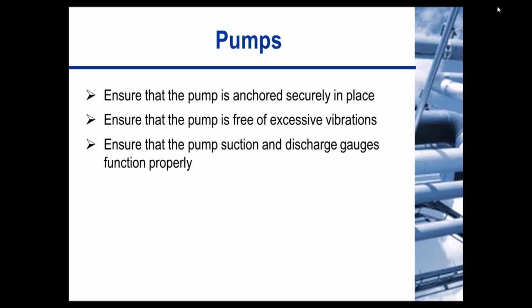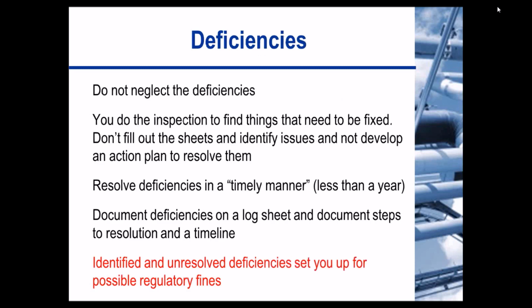Now, let's talk about deficiencies in general. First of all, we don't want to deflect or neglect these deficiencies. So when you do an inspection and you find things that need to be fixed, these are items that you need to resolve in a timely manner. This is often less than a year. Document deficiencies on the log sheet, and you need to document the steps that you go through to achieve resolution and the timeline. Remember, if it's not documented, it didn't happen. So this is a key part of your process.